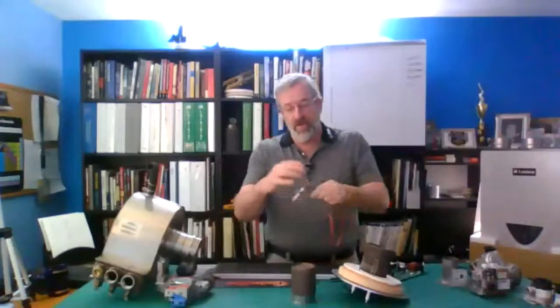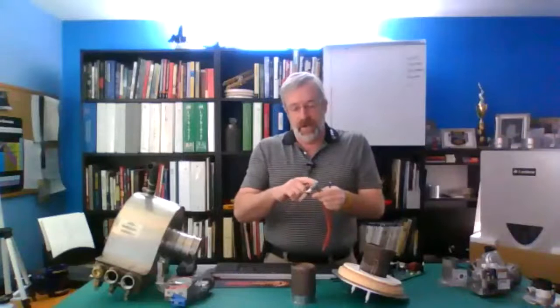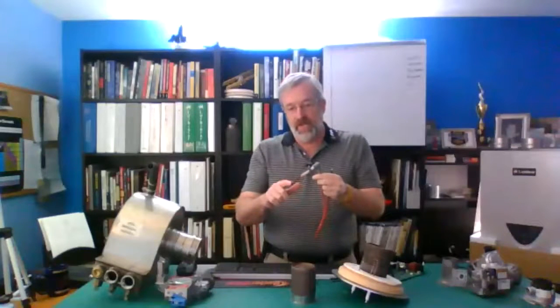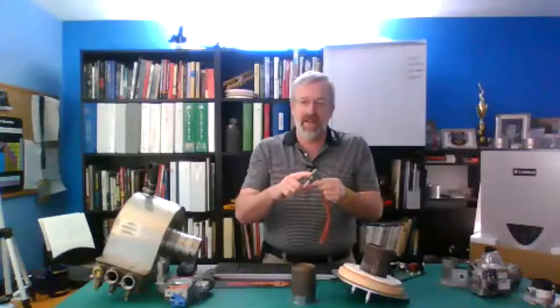There is a ground wire that'll go on here. If you can't tell if it's sparking, take it out of the cabinet and just let it hang outside of there. Leave the ground connected. The reason you need the ground is, for it to spark, I'm going to send that voltage out this direction, and it's going to actually come right back to the ground. If I disconnect that, the spark can't make its way back. So make sure you keep that connected.